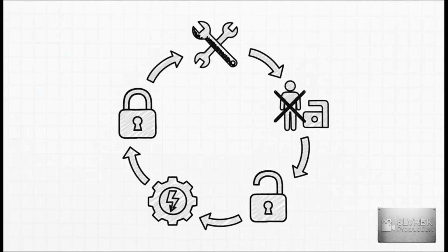Now, what if you need temporary power for testing or positioning? Well, you have to follow a strict 5-step loop. Clear tools and materials, clear employees from the area, remove devices per standard, energize and test, and then immediately de-energize and reapply your devices. Protection must be immediately restored.